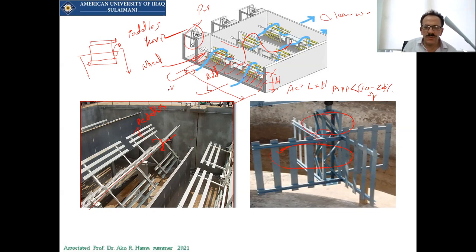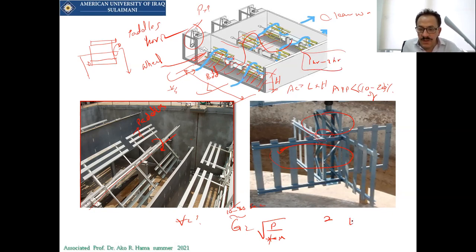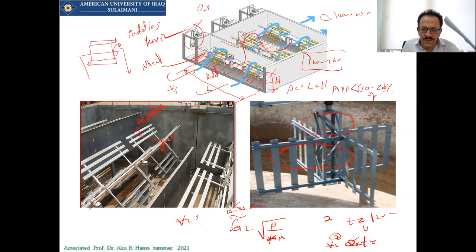The water will stay for one to two hours in this tank, so I have the time T = one hour. Volume equals Q times T. After having the volume, I substitute G (10 to 80) to find P — the power needed to rotate the paddles. The power per paddle depends on the area of the paddles, the distance between paddles, the thickness, the width, the diameter of rotation, and the velocity of the paddles in RPM.